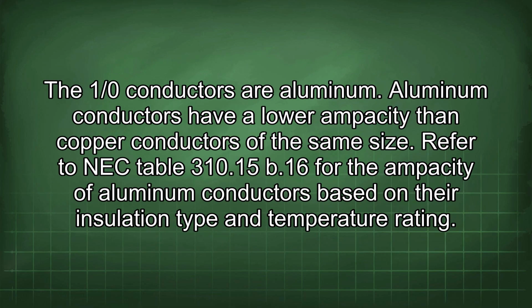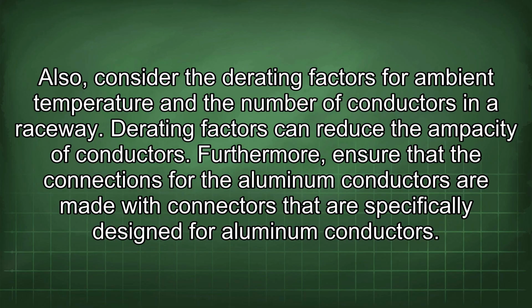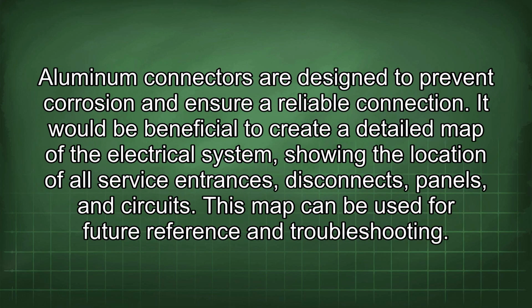The 1/0 conductors are aluminum. Aluminum conductors have a lower ampacity than copper conductors of the same size. Refer to NEC Table 310.15(B)(16) for the ampacity of aluminum conductors based on their insulation type and temperature rating. Also, consider the derating factors for ambient temperature and the number of conductors in a raceway. Derating factors can reduce the ampacity of conductors. Furthermore, ensure that the connections for the aluminum conductors are made with connectors that are specifically designed for aluminum conductors. Aluminum connectors are designed to prevent corrosion and ensure a reliable connection.